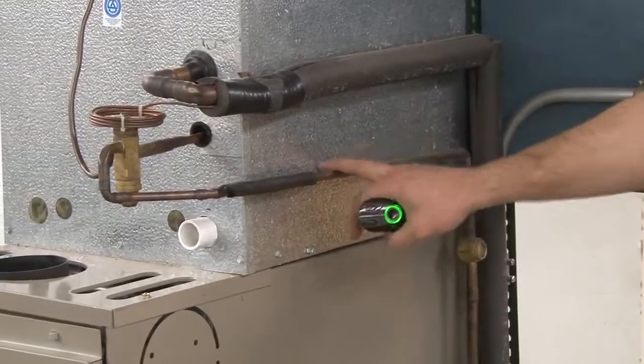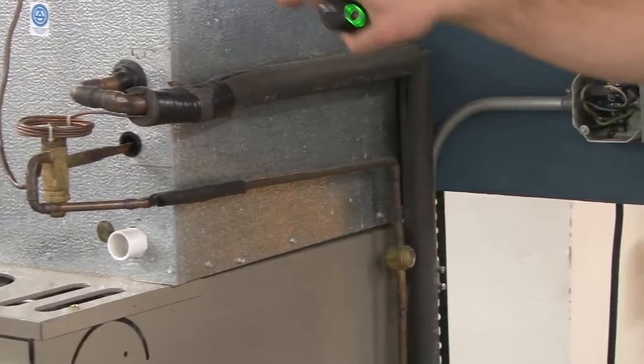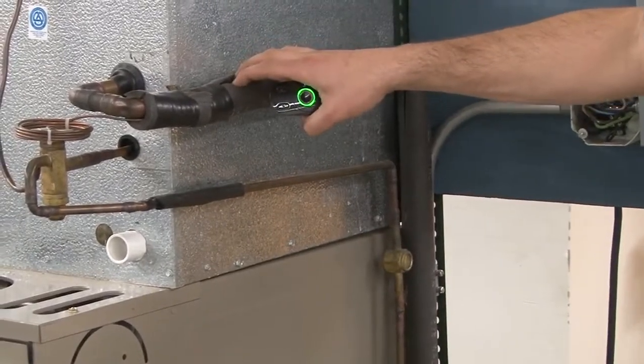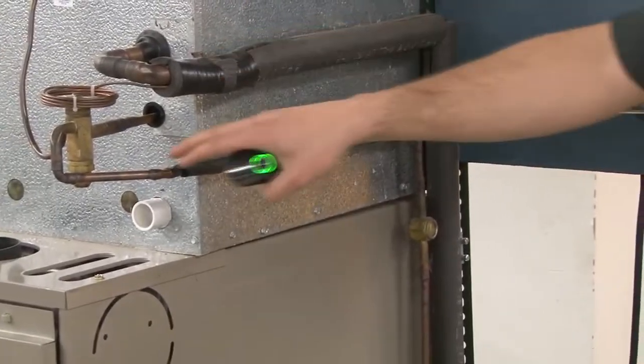Your line set hooks the two together: your liquid line, your small line, and your suction line, your vapor line, which is the bigger line. These happen to be 3/4 and 3/8.